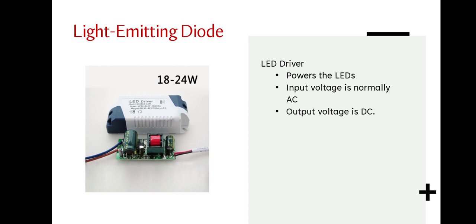Constant voltage LED drivers are used with LED circuits designed specifically for a constant voltage during operation. The most common types demand 12 volts, 24 volts, or 48 volts. Constant voltage drivers are normally used with LED fixtures that already have a built-in current driver. Their job in this situation is to supply the necessary stable input voltage.